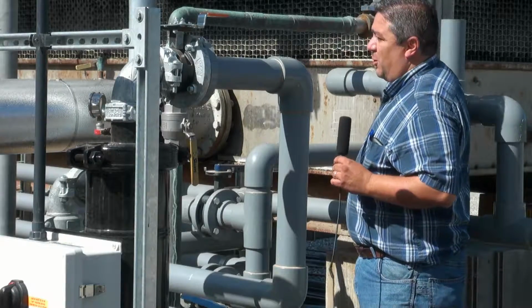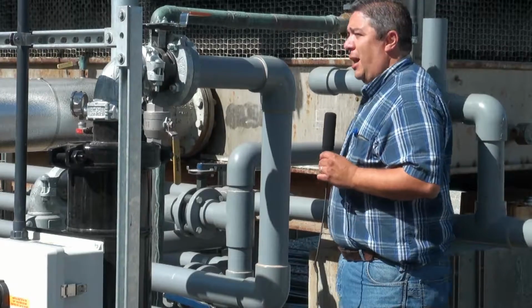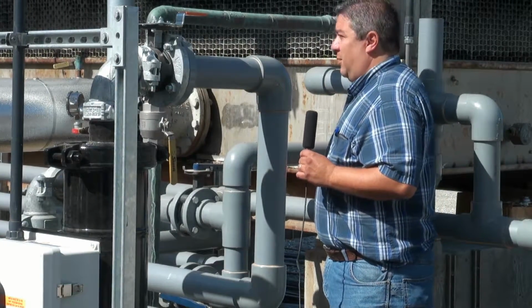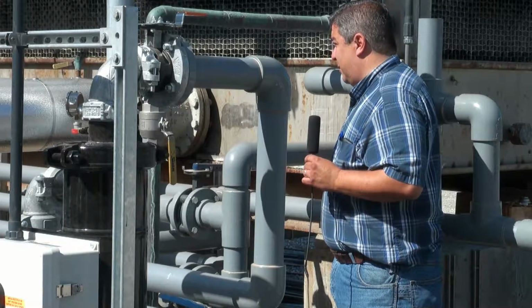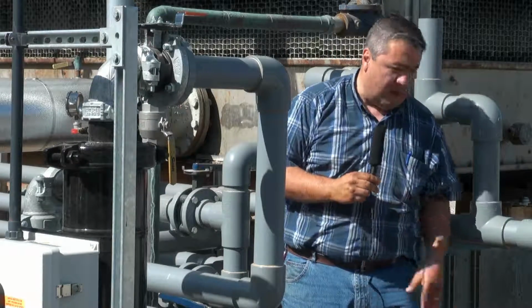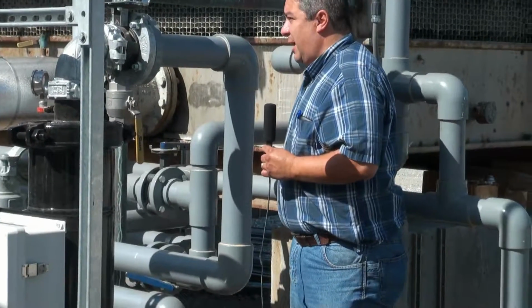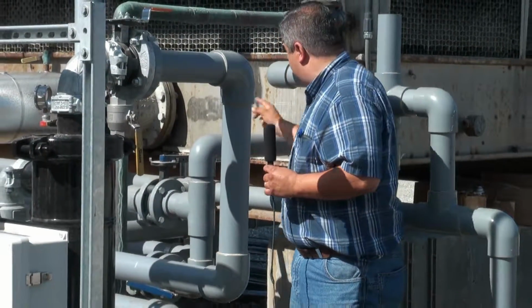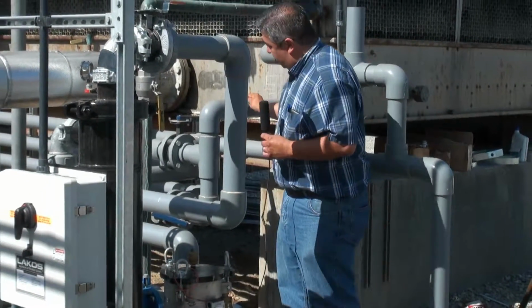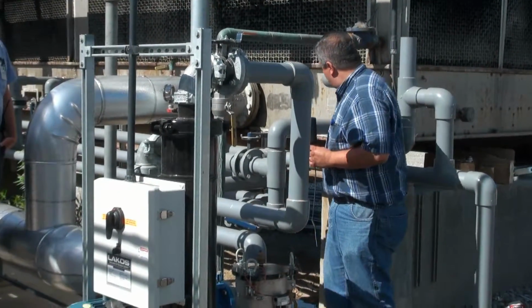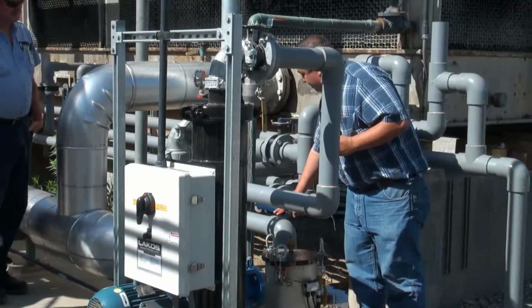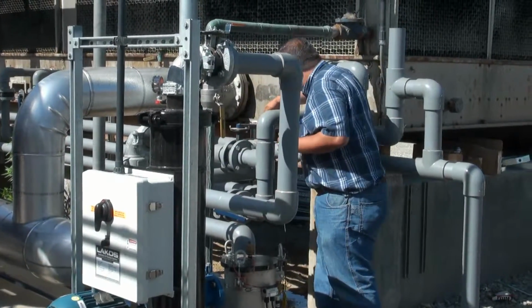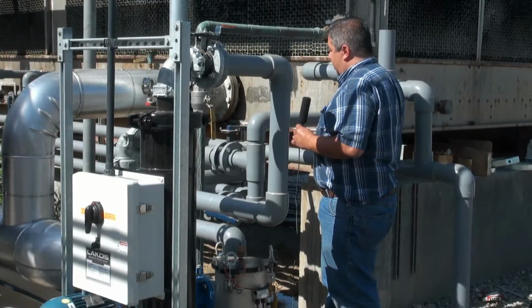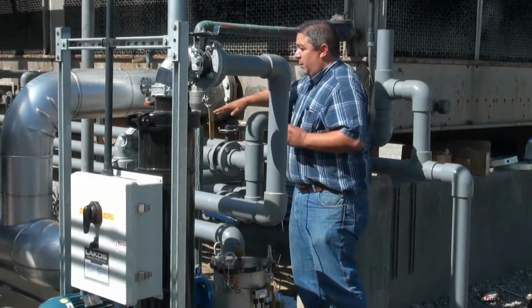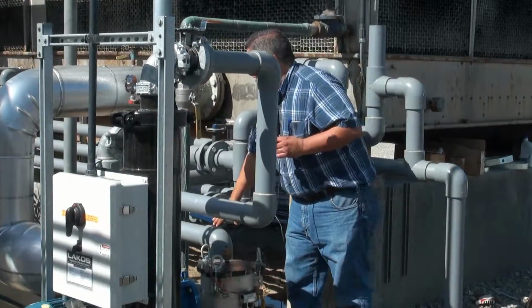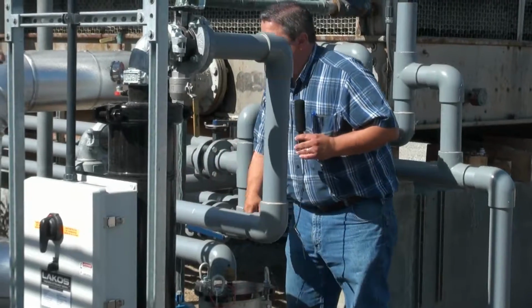So there's an overflow line and a drain line on this tower. When the tower gets higher than it should, it overflows out, right? It drains itself out, comes out into the trap and out of the drain. This is the drain. You want to drain the tower, you pop the valve, drain everything in the tower. What they did here, if you look, is they paralleled the drain to the system, right? So if you want to drain the tower, you pop this valve right here, and it drains the tower, right? So that's why it's closed. But because you're working the separator, this valve is open, so they take that same water, parallel off, and go back to the separator.